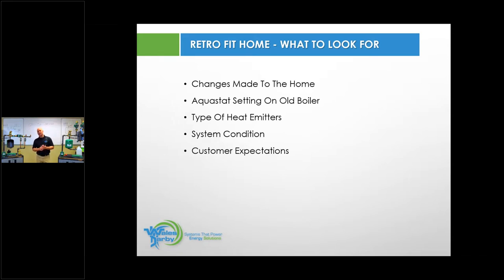System conditions. And I'm not just looking at system conditions from an outside perspective. I'm thinking of what's going on inside of those pipes. And what do I need to do to treat those to make sure that I can deliver good, clean water through those pipes, which will transfer energy better to the home. And in addition to that, it's important to know, because I have a condensing product here and I may take all the dirt and debris from the home and deposit it into my condensing boiler and have a premature boiler failure. So that's what I'm talking about here when I'm talking about system conditions.